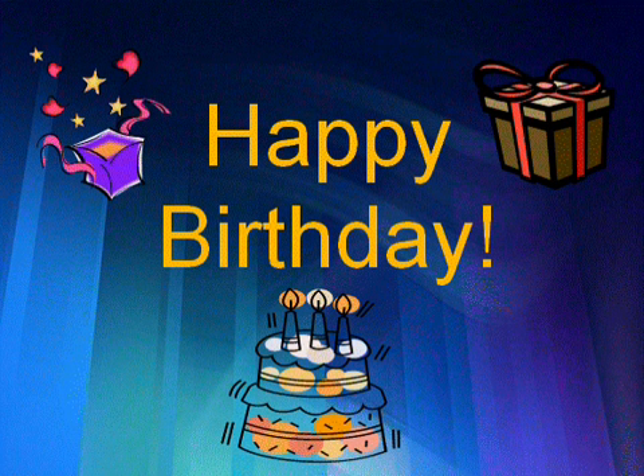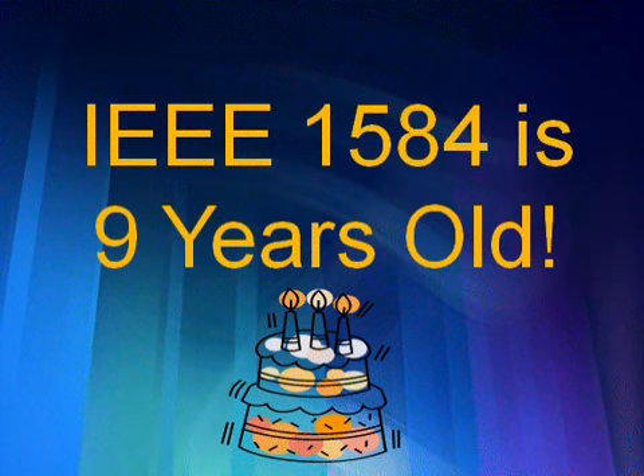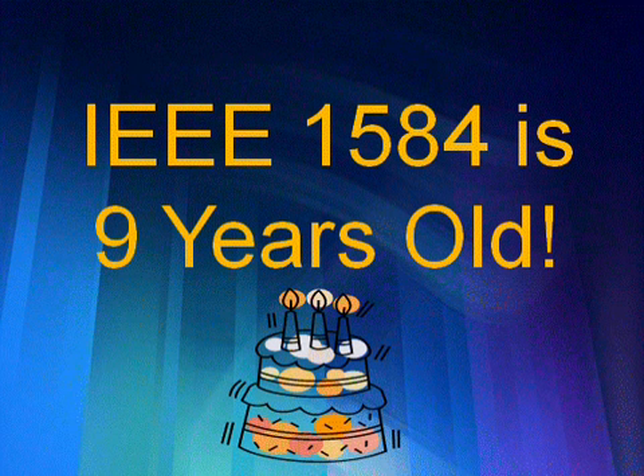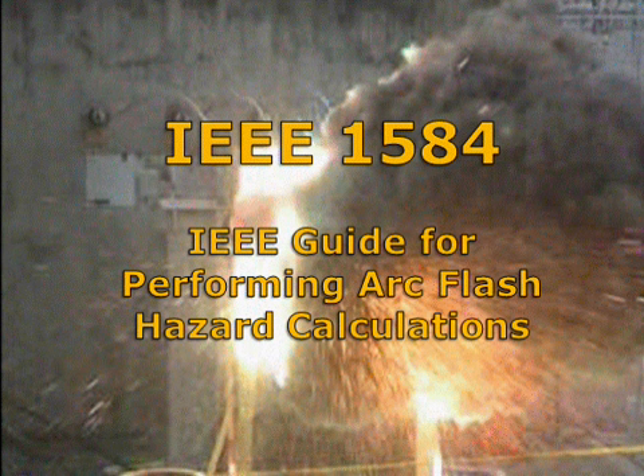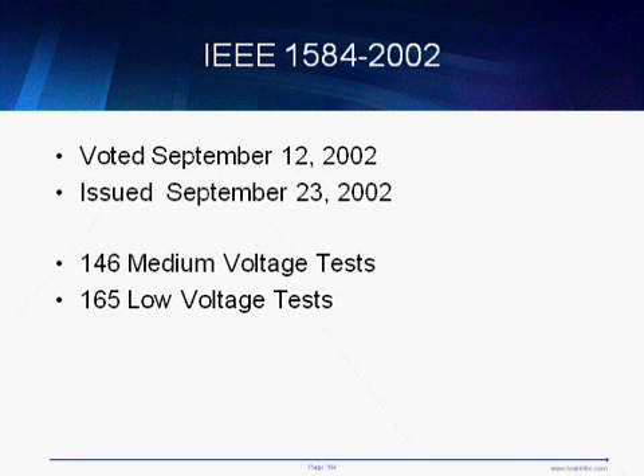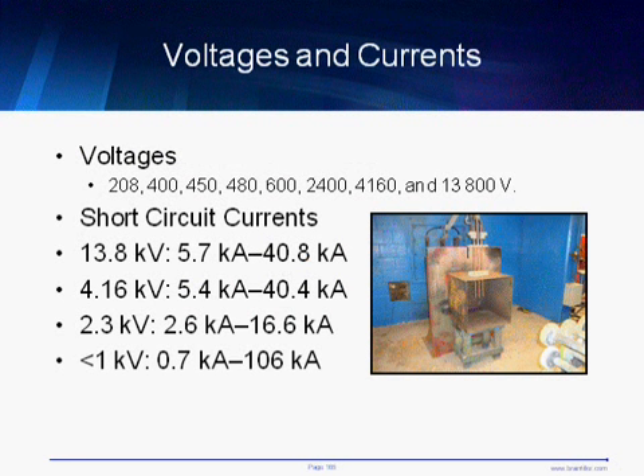We have a birthday party coming up. And for the birthday party, you might be thinking, what does this have to do with what we're talking about? Well, in a couple of months, IEEE 1584 is turning 9 years old. And since that time, when IEEE 1584 first came out, the IEEE Guide for Performing Arc Flash Hazard Calculations, we have learned a lot. When this guide came out, it was one of the most amazing documents, just my opinion, that I have seen in a long time, because it covered and answered a lot of things that, well, we didn't have an answer before. And this was based on over 300 tests, and it provided the equations that we still use today for arc flash studies.